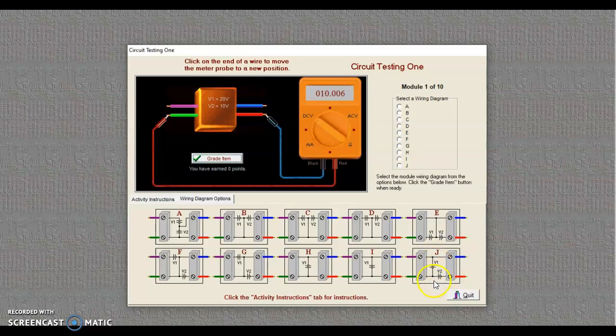But I don't know which one it is without switching my probe. So I'm going to choose the best option here. If it was F and I went to this blue wire up here, I would see zero volts. If it was G and I went to the blue wire, I would also see zero volts. So maybe moving my black to the blue wire is not the best. If it was J and I moved it up here, I could see 20 volts in that setup.